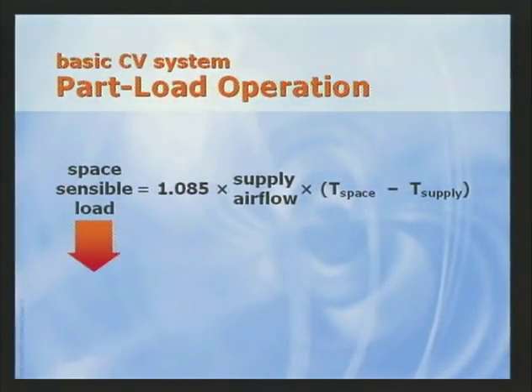Well, the outdoor dry bulb temperature is lower, so the sensible cooling load in the space drops because conduction heat gains are less. There may also be a decrease in the solar load depending on the time of day and orientation of the windows. So as the sensible cooling load in the space decreases, this basic constant volume system continues to supply a constant quantity of air to the classroom. In order to avoid overcooling the space, the supply air temperature must be warmer. Supply air temperature is increased by reducing the capacity of the cooling coil. In the case of a chilled water coil, this is typically accomplished by modulating the control valve to reduce the rate of chilled water flow through the coil. In a typical DX application, a compressor cycles on and off.